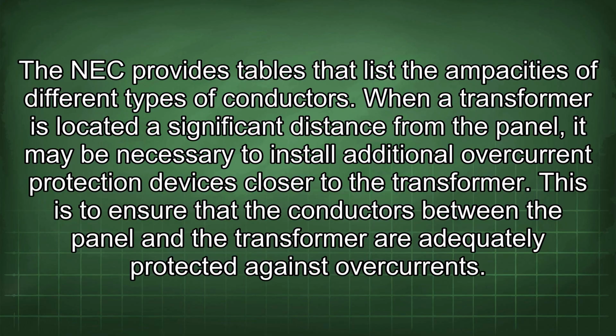When a transformer is located a significant distance from the panel, it may be necessary to install additional overcurrent protection devices closer to the transformer. This is to ensure that the conductors between the panel and the transformer are adequately protected against overcurrents.